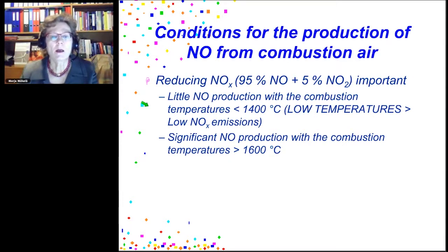Temperatures less than 1400 Celsius degrees results in less nitrogen monoxide. Temperatures higher than 1600 degrees results in more nitrogen monoxide emissions in the combustion.